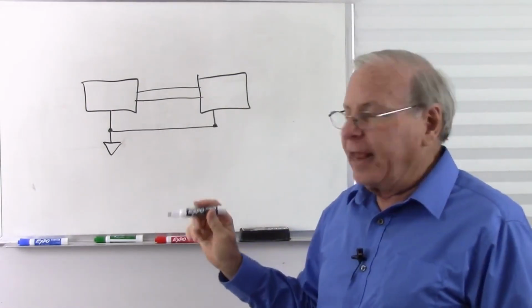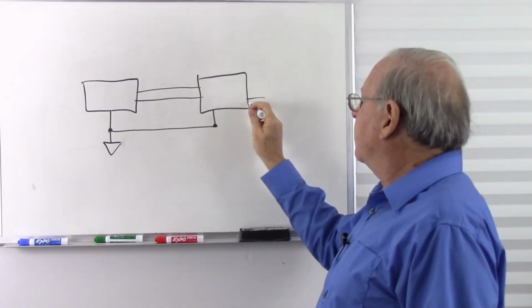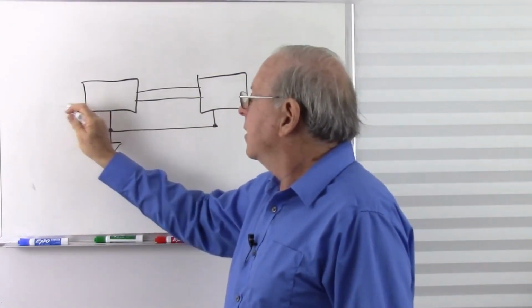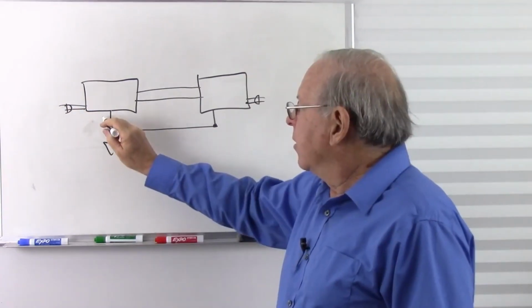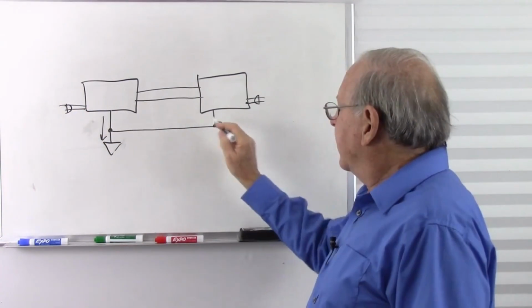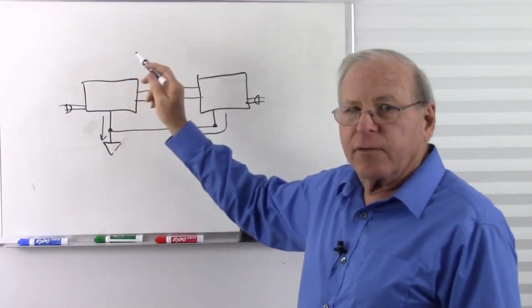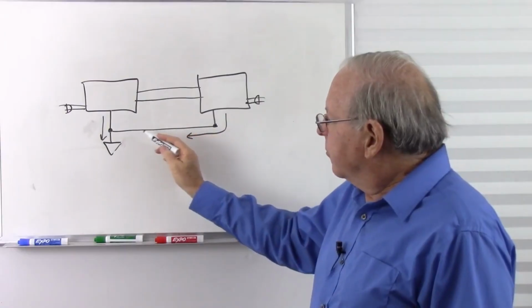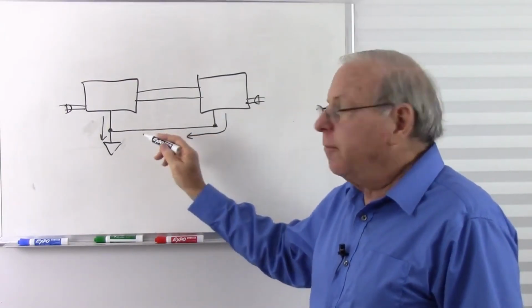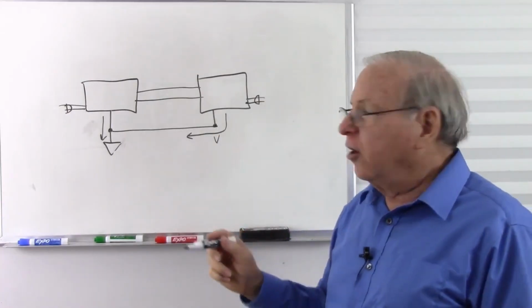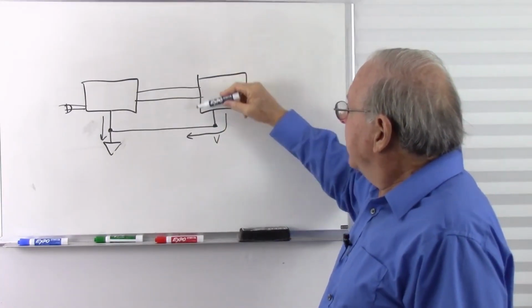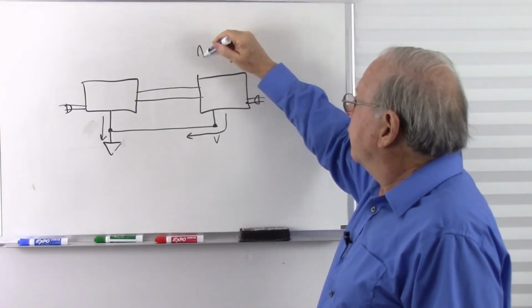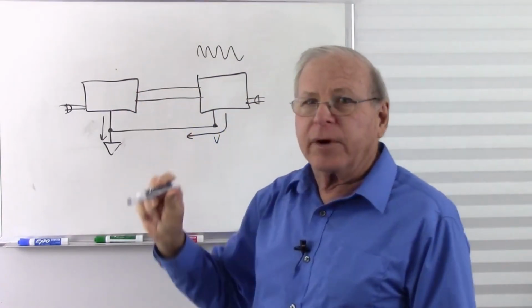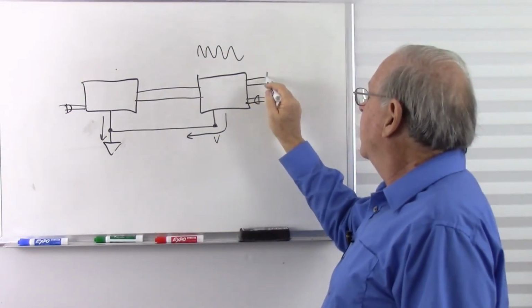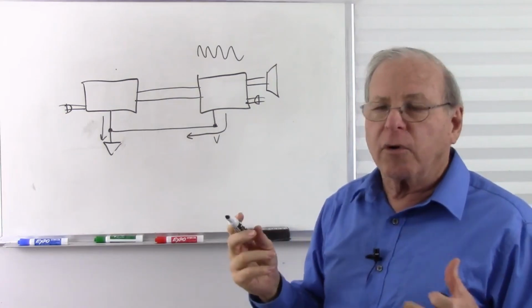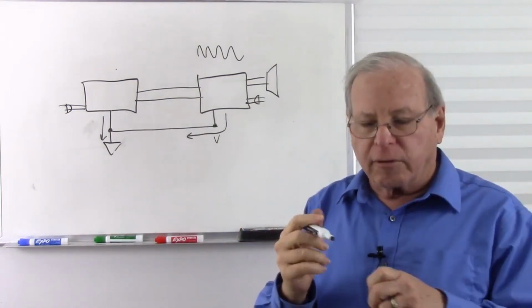And there's two problems that can happen with this. One, we have power supplies in here that are plugged into the wall. And we get alternating currents going to the ground. And it's going to flow that way, and here's another alternating current, of course, going back and forth and back and forth. Well, you can see there's a substantial amount of wire here, so we're going to get some voltage here, some alternating current there. So basically, this whole system here has a voltage that's going up and down and up and down and up and down compared to that one. And that can result in us hearing a 60 hertz or 50 hertz hum, depending on where you are in the world, on our speakers, or we can see those horizontal bars in our video.